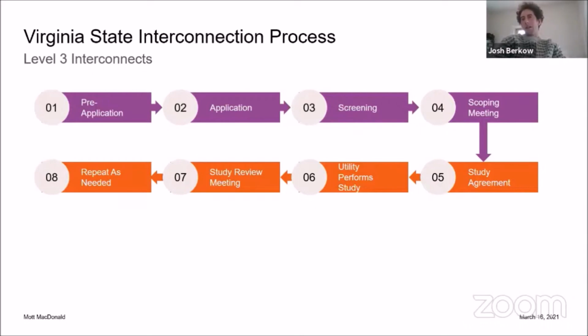In Virginia's case, I'm only presenting the level 3 process, because levels 1 and 2 are much more straightforward and have fewer pitfalls. Generally, we recommend that wherever you are—whether it's a level 1, 2, or 3 interconnect, or a PJM interconnection—you reach out informally to whoever the regulator is to understand the process and your point of interconnection. As we'll discuss later, that's the best way to get information about where your POI is and what could tie in there before you spend money trying to get a study through.